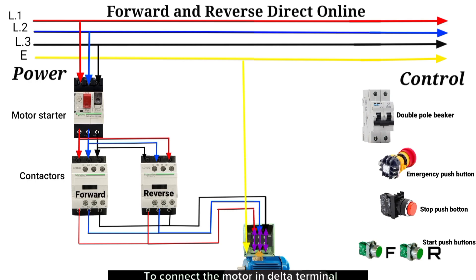To connect the motor in delta terminal connection, use these step connections: U1 to W2, V1 to U2, and W1 to V2.